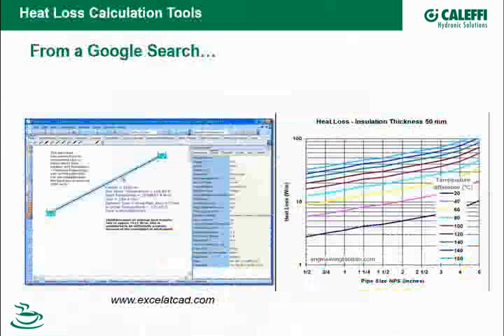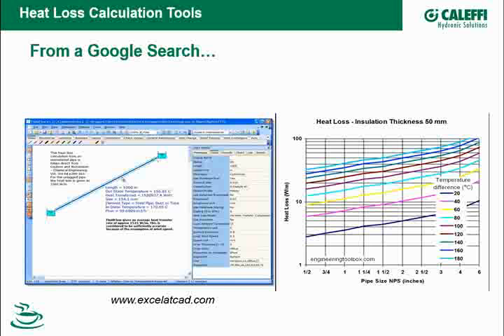So there's two things that I've noticed that seem to get overlooked or forgotten sometimes when you're doing a hydronic system, either a hot water system or chilled, but more probably a hot water system. And probably more so on the residential side. I would say most commercial jobs, if it's done by an engineer, there's going to be an insulation spec written up for the job that requires a certain thickness and a certain type of insulation. And generally, another contractor would be pulled in to do that.